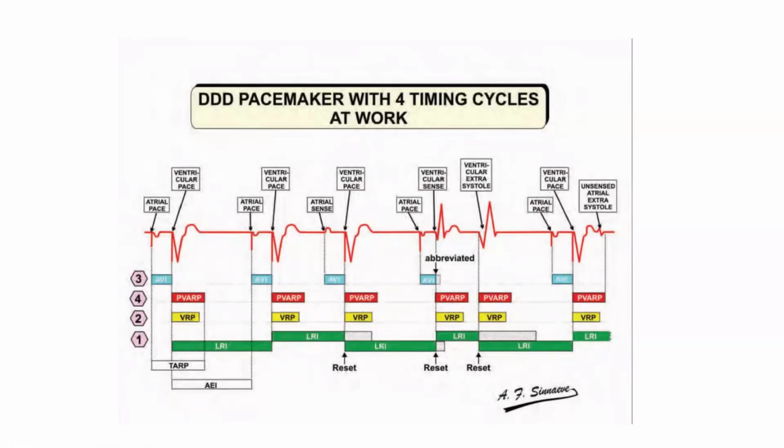Why is it pacing faster? Because it's now tracking. It's following the atrial lead. The pacemaker acts at the lower rate you programmed, like 60 beats per minute, only if it's pacing both atrium and ventricle. But remember, the main order you give the pacemaker is to follow the atrium, to regain for the patient his sinus control of his rhythm. So if the sinus node increases its rate, it will increase the heart rate. Decrease rate, it will decrease the heart rate. And you don't allow it to decrease below a fixed point like 60 beats per minute. But if you have a normal sinus node function with fast P waves, the pacemaker will follow these waves.